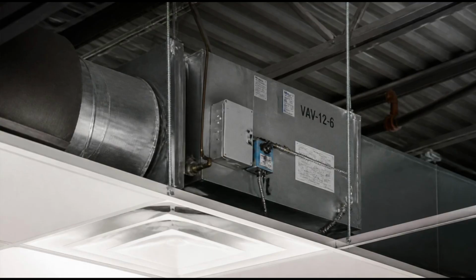Stale indoor air can be moved out of the building. Some of the return air is not recirculated. Instead, it is exhausted, pushed out of the building through dedicated exhaust systems. This is particularly important in areas where air quality concerns are highest, such as restrooms, kitchens, or spaces where chemicals or strong odors may be present. Exhausted air leaves the building and is replaced by a corresponding amount of fresh outside air, maintaining the pressure balance and ensuring proper ventilation. That loop helps keep the building comfortable in a steady way.